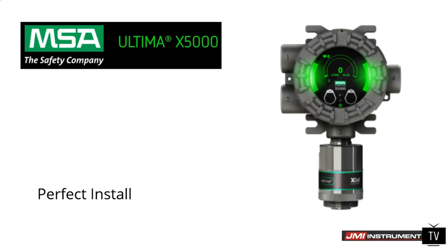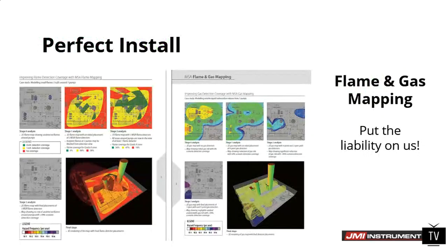We also have capabilities to pump a sample from maybe an area that's too hot, too cold, too wet, too dry, and bring that sample, condition it, and bring it to the sensor itself. So we have a nice clean sample to analyze. And then one of the other things that we might want to talk about is looking at flame and gas mapping.